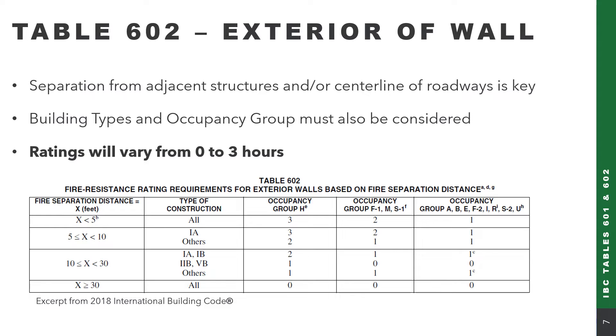In Table 602, the first column is the fire separation distance, broken into four categories: less than 5 feet, 5 to 10, 10 to 30, and greater than or equal to 30 feet. The second column focuses on construction types. If we're less than 5 feet, construction type does not impact the fire rating requirement. Similarly, if we're greater than or equal to 30 feet, it's not going to impact fire rating requirements. However, construction type does matter between 5 and 30 feet.